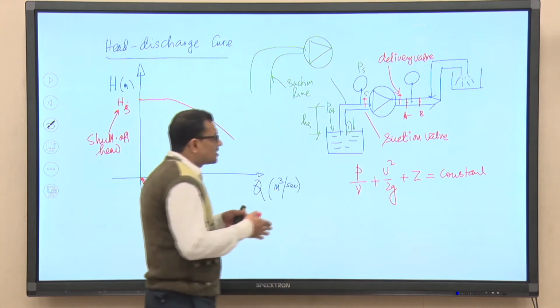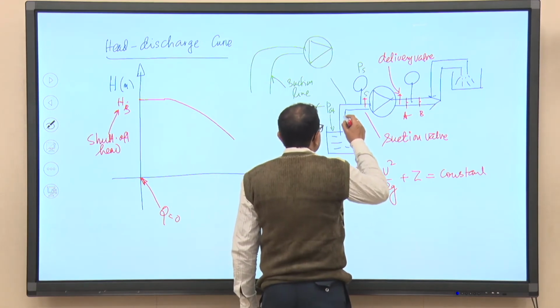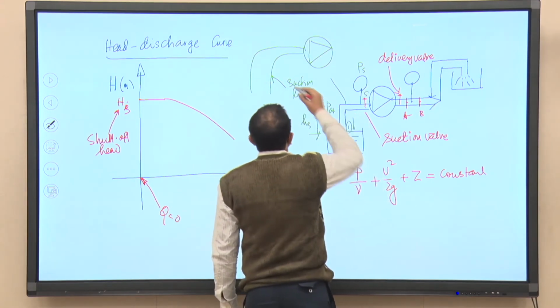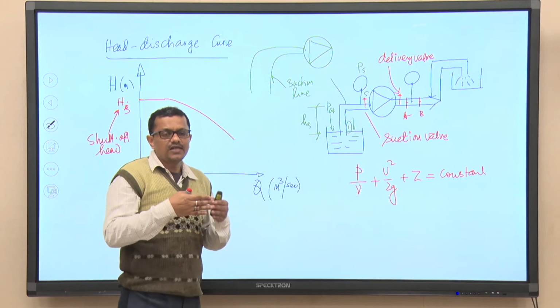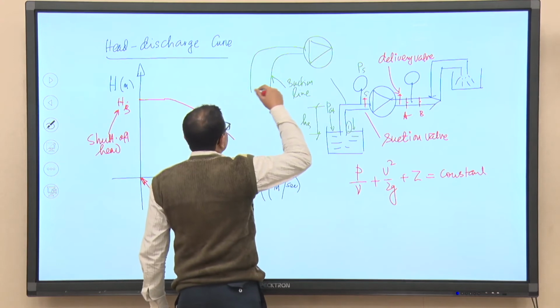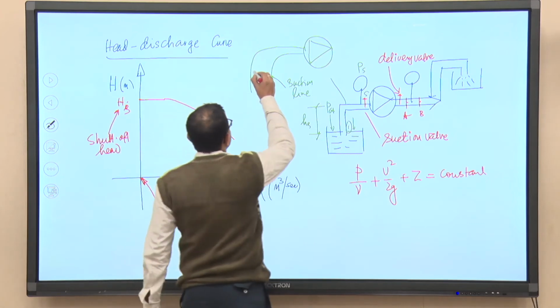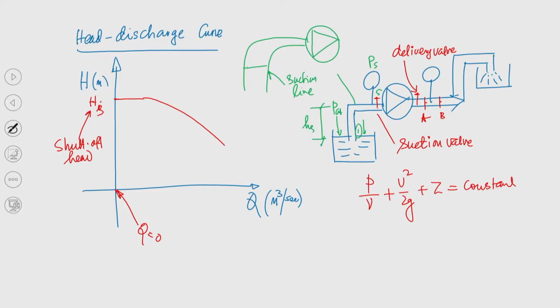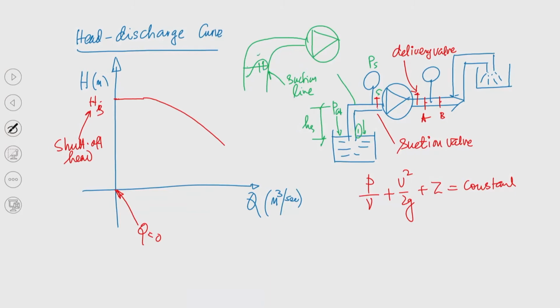But it is not the case, I mean this is fine. Question is, pressure reduces, but here the liquid is allowed to flow through a pipeline. So, definitely the liquid will be in contact with the boundary, as a result of which there will be frictional losses and flow velocity will be highly non-uniform in the suction side. And because of this, if I take this particular cross section, maybe velocity here is less and velocity here is high and this is less. So, a kind of recirculation eddies will form in this suction pipeline.